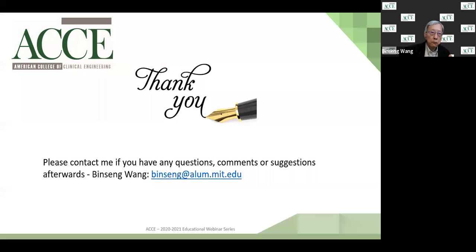Now, for the maintenance portion of the defibrillator, there is one thing that I highly recommend: follow manufacturer recommendation until you have enough data to decide to make any changes. That is checking the battery. The battery is a rechargeable battery. If it's not lasting long enough, if it's not going to hold charge, then you need to replace that. It is a wearable part that needs to be replaced, so you need to schedule that. Also, it does not hurt to check the output of the defibrillator periodically, and that can be done annually or every 18 months, even if you want to stretch that. And I don't think there is a significant savings in time in doing that, so I would rather do that out of an abundance of precaution.